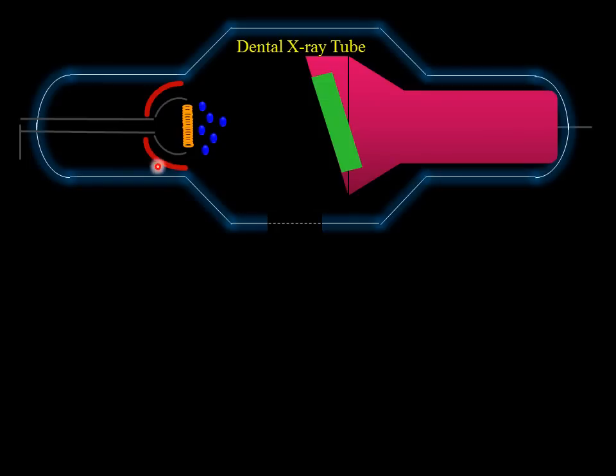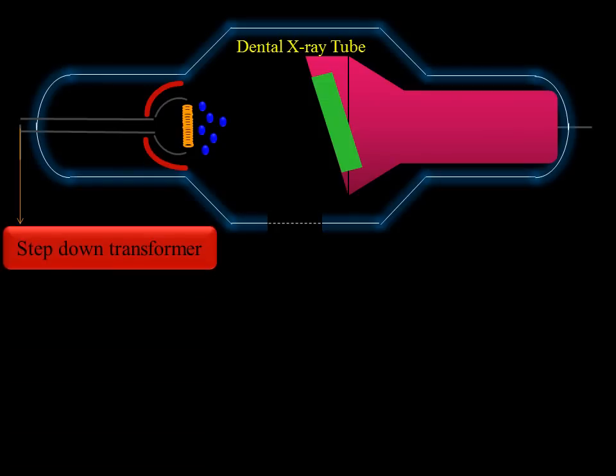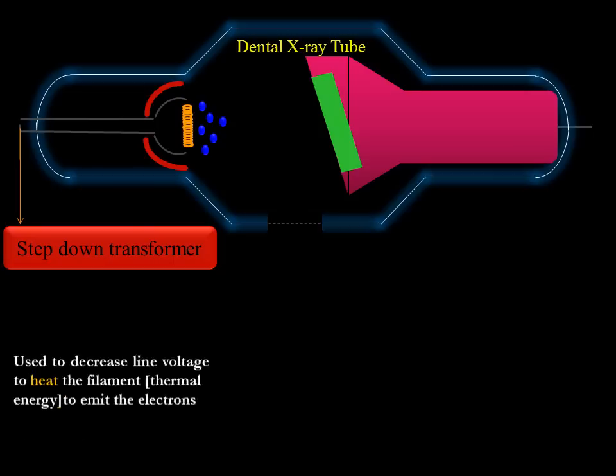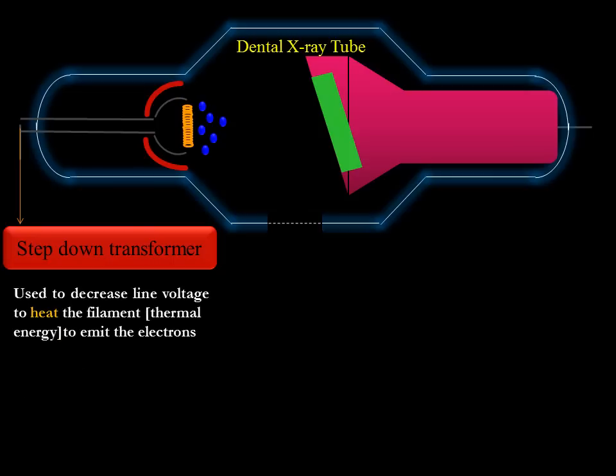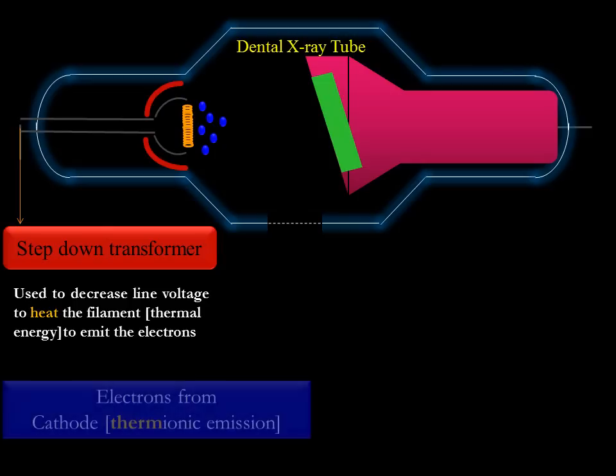The cathode of the dental x-ray tube is connected to a step-down transformer, which is used to decrease the line voltage to heat the filament to emit the electrons. The electrons produced are said to have been produced by thermionic emission.